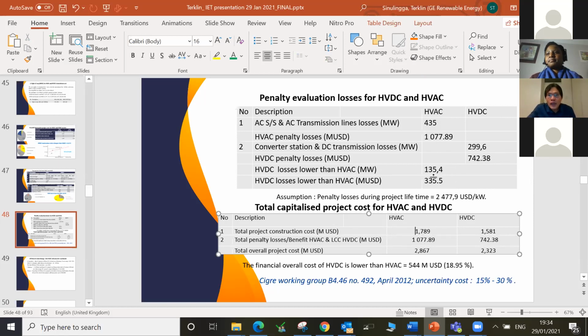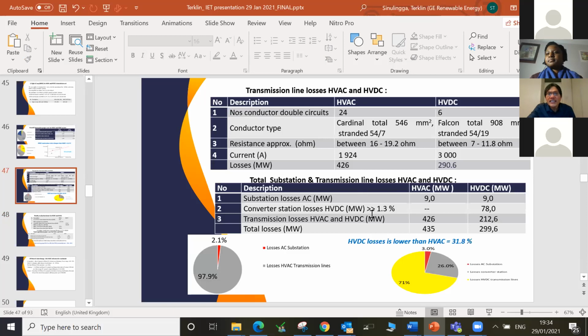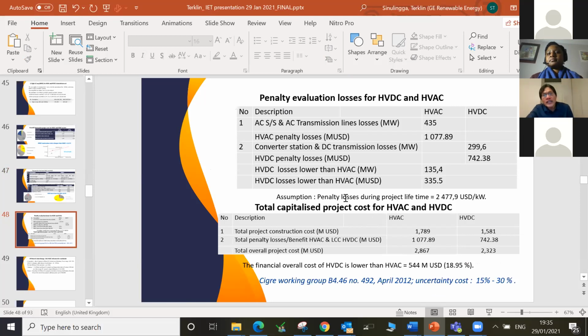Therefore, in my calculation, I got the total losses of AC as 435 and the total losses of DC as 299.5. I have to transfer these losses into money for the investor. There is a convention; this is the industrial practice for lifetime. They can use 2,500 or 2,600, depending on the convention used. But in my assumption, I put 2,400. By this, I can compare the monetary losses of AC and the monetary losses of DC. I don't know if it answers the question here.